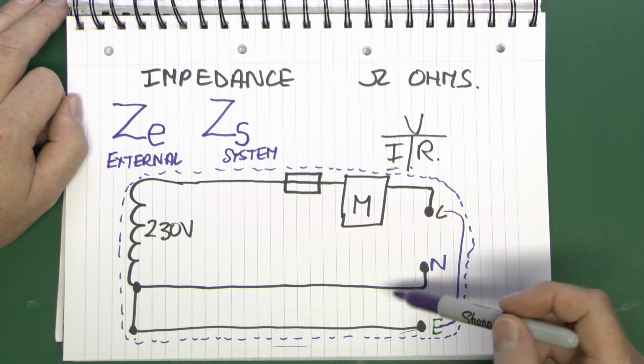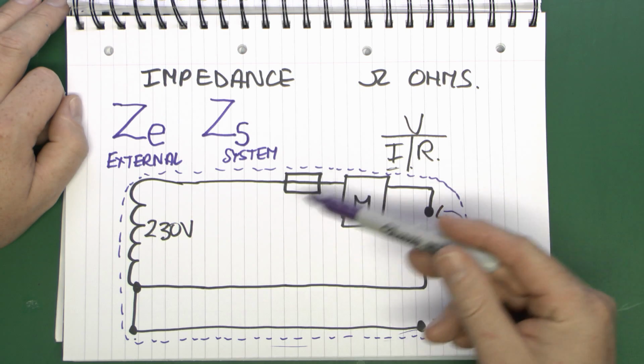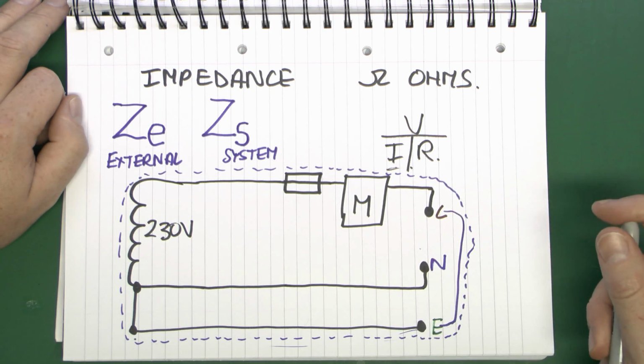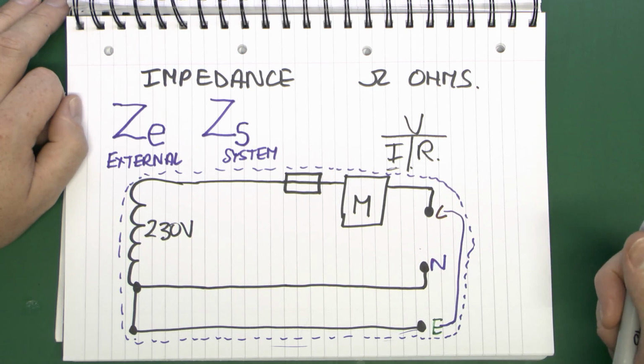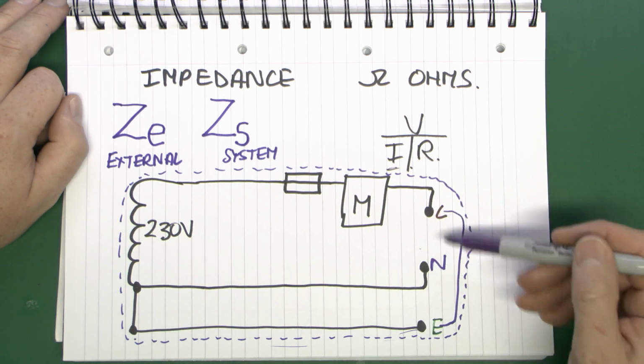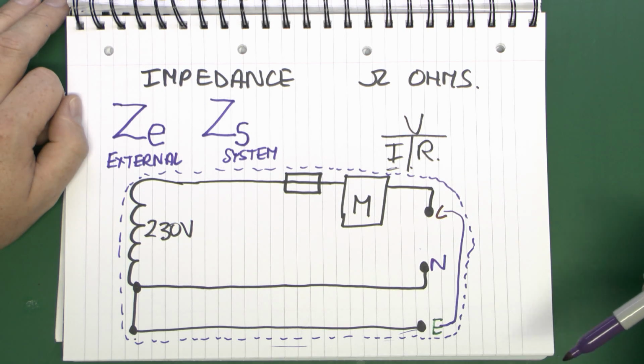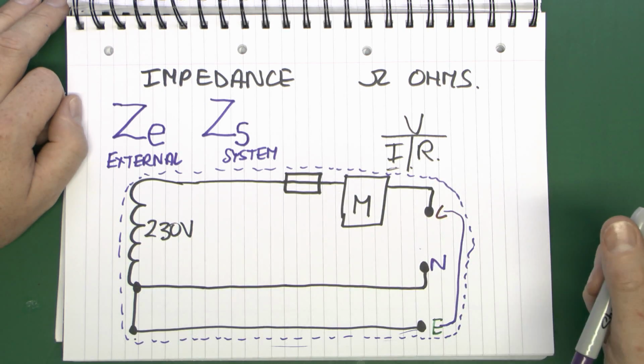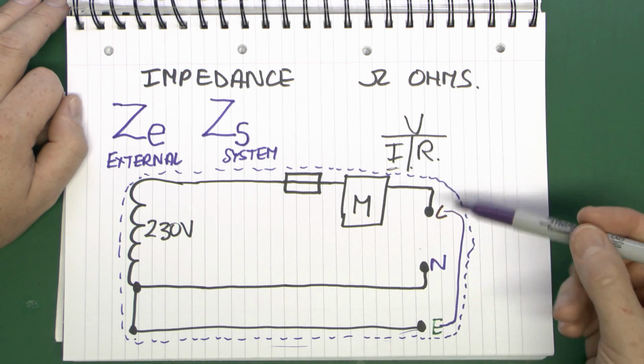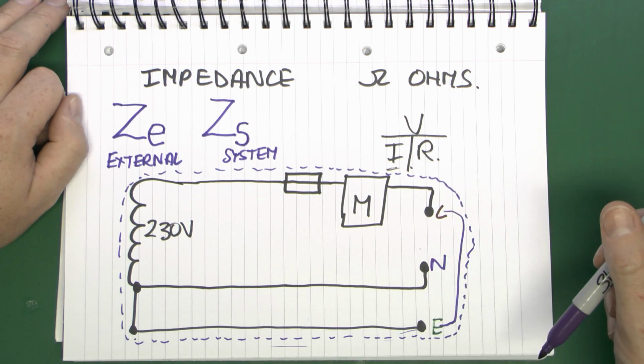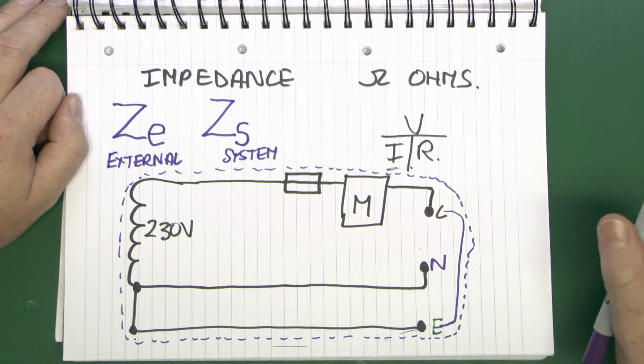And another method is actually to inject a current into this and again measure what kind of voltage drop, whatever you get. So not something you generally have to be concerned with, because if you've got the actual device, it's a question of just connecting it to the terminals and pressing the button. But essentially that's how it's going to do it, either by putting a current in or applying a known load to the end and seeing what kind of voltage drop actually occurs.